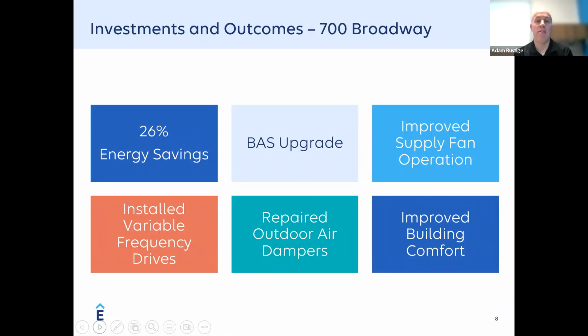As you can see from the slide, 700 Broadway, in the year 2021, saved 26% energy compared to 2020. The lion's share of the work that we did was upgrading the building automation system. The system itself was over 20 years old, and it was time for an upgrade. One of the benefits of upgrading the BAS: the building has two really large air handlers. The motors on the supply fans are 400 horsepower each, so they use a tremendous amount of energy. We were able to improve the operation of the supply fans, and that saved a significant amount of energy.